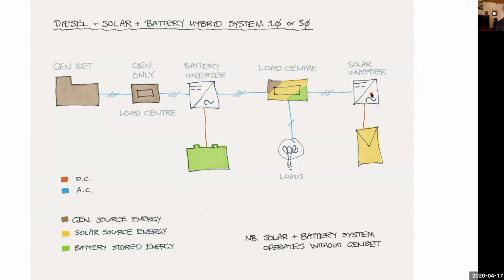Now, we talked about this in earlier webinars, that solar inverters actually control the array. So you don't have to worry that your array has 10 kilowatts of PV connected. The inverter determines how much of that will be converted into AC power. It doesn't have to be spilled anywhere. It just doesn't get produced. So when that communication is occurring, the battery inverter is shifting the frequency. It's basically telling the solar inverter, reduce your output to X, reduce it by 50% or reduce it by 80%. And that way it can control the charge rate for the battery. Now that's historically the oldest way of controlling across an AC network.